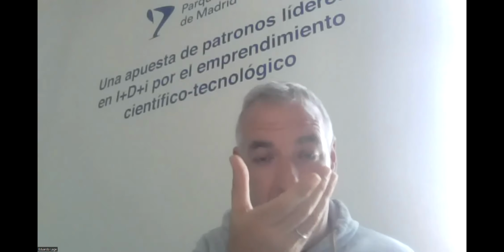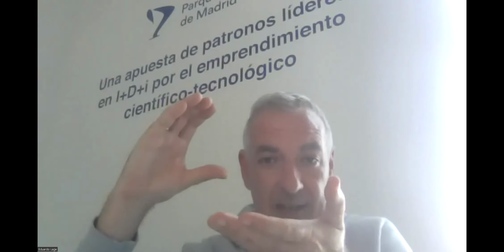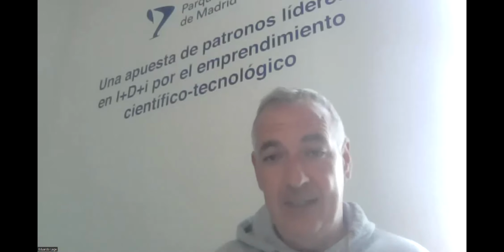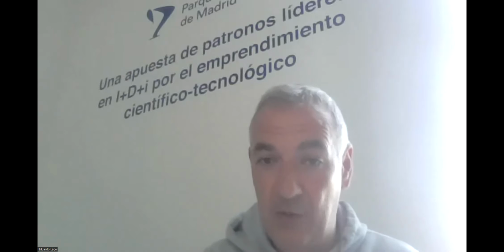There have been several questions about the use of the device in children and also the weight, recommendations on how to use it in children, the limitations, etc. Well, regarding the weight of the device, it is 1.3, 1.4 kilograms. It's not exactly 1.5. And the measurement time is 10 seconds after we align. So sometimes with small children we help them by holding the device on the back side. We align the device, we hold it with our hands, and the operator also puts a hand under the device just to help the children during the measurement. We can do the same if the patient is in a wheelchair or has some kind of disability. This is the standard way we work.